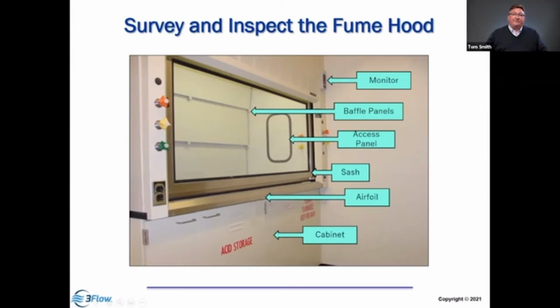Then we have the baffles in the back of the hood. The baffles are aligned to help remove the contaminants from inside the hood. If they're not properly installed, they're not going to function right, and we're going to get issues with performance. And then we have these access panels. The access panels provide access to the plumbing and other features that might be in the sidewall of the hood. If we're missing an access panel, then it's going to leak air into the hood and it's not going to perform properly.